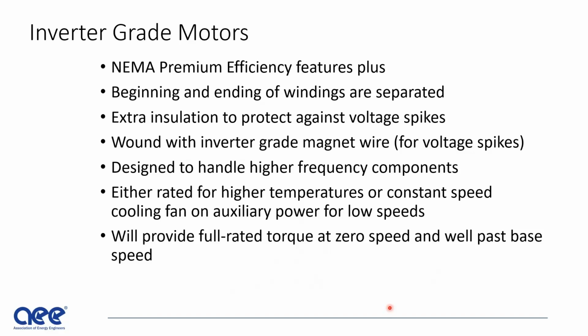Inverter grade motors: when you are using a VFD or an inverter, it's best to use a NEMA premium efficiency motor with the beginning and ending windings that are separated. Up until the inverter grade motors were developed, the windings always started and ended together. And with the voltage spikes present with VFDs, you have to protect against that, and you always want those beginning and ending of windings to be separated. Extra insulation is also added to protect against voltage spikes, and inverter grade wire is used, which has a heavier insulation and is designed for higher frequency components, which create losses. So heating is a big issue.